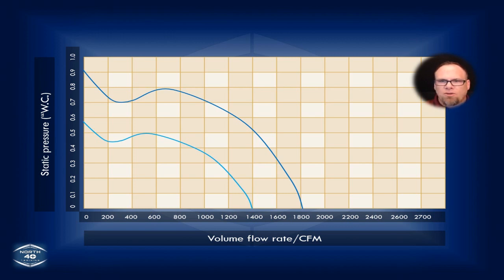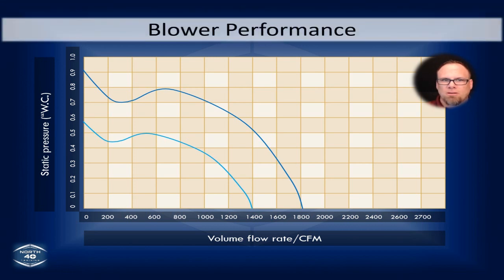Well, if you were to use your manometer and stick it in those areas of the furnace where you made the penetrations before and after the blower, like we just talked about, you'll find a resistance reading. And on that resistance reading, you then take that back to the chart, and that chart is going to tell you what the CFM value is for that resistance. Okay, and before we move off of this chart, we're going to talk about this a little bit more, but there's something that we really need to address, and that is filters.